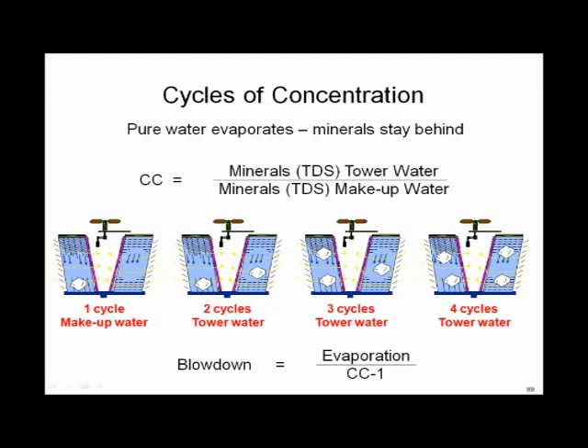And I've now got 2 cycles of concentration. I've got 2 rocks and 1,000 gallons of water. I evaporate that 1,000 gallons of water down again in my cooling tower. My 2 rocks stay behind. And what do you do? You bring another 1,000 gallons of water in with another rock. I've got 3 cycles of concentration, 3 rocks in 1,000 gallons of water. If I evaporate that 1,000 gallons of water all the way down to the bottom, my 3 rocks are still there in that tower.